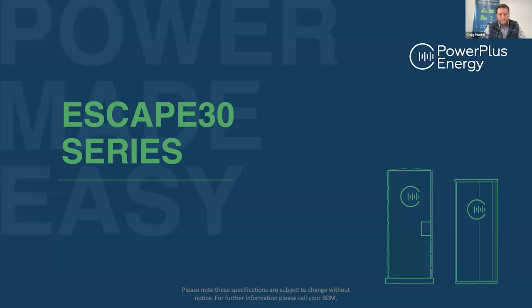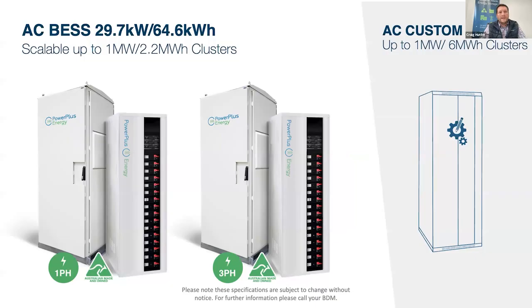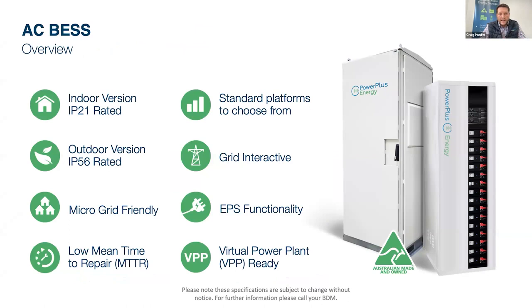So I'll just touch a little bit on the Escape 30 series. The Escape 30 series is very similar in lots of ways to the Escape 20. This one is a little bit different in size. It's 29.7 kilowatts output, still the same 64 kilowatt hours of storage. And what we can do with this is scale it up to 1 megawatt clusters for on-grid applications. So I mentioned before, it's very, very similar. So there's an indoor and an outdoor version.